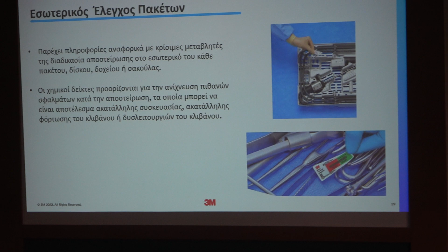In addition to biological indicators, we are well aware that they show us the ability to kill, but we still need more information from inside the pack, because we are not always sterilizing the same type of instruments or the same type of bags. We have textile packs, and maybe at the same time we have heavy sets. And therefore we have to make sure that the killing steam is reaching inside and all sterilization conditions are met: time, temperature, and saturated steam. And chemical indicators help us in this process.